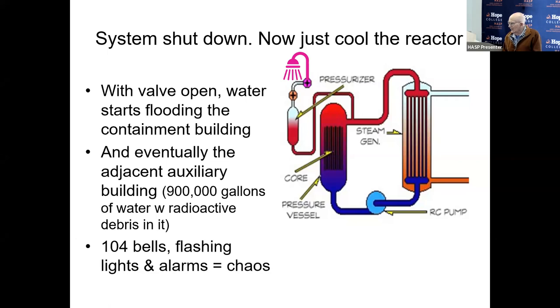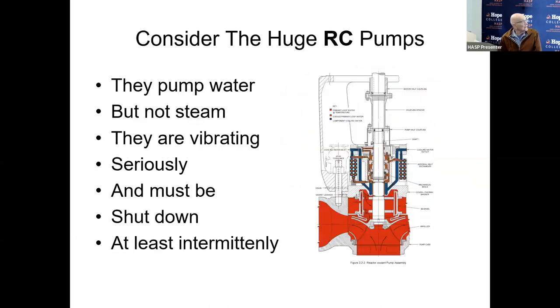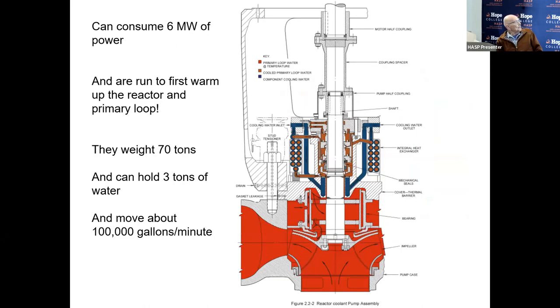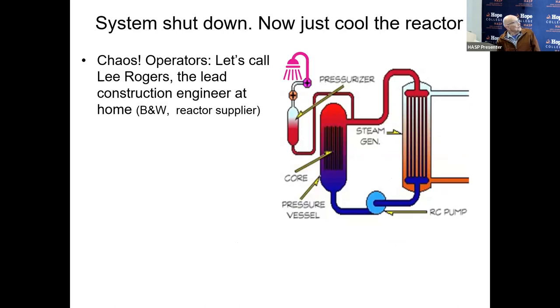Oh my God, the alarms are sounding everywhere. There are 104 bells ringing, flashing lights and alarms, chaos. Now, those pumps pump water, not steam. They're vibrating, and they've got to be shut down intermittently. I mean, these pumps weigh 70 tons. They can hold 3 tons of water. They can move 100,000 gallons of water a minute. They're huge, they're important, they're somewhat delicate. So you're careful what you do.